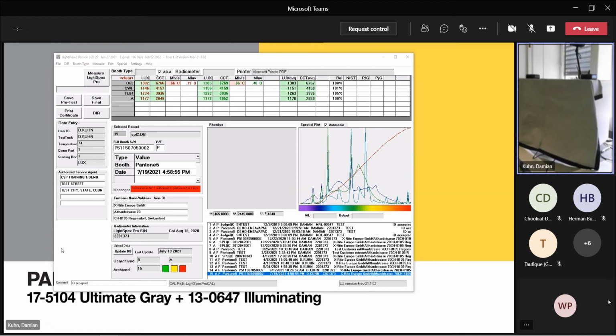So basically, your first step, if you would like to certify this product for a customer, is to connect your Lightspex Pro, position it in the center of the booth, and ensure the first light source is warming up. Then you would start your software, go to booth type, and select the booth you would like to certify. You're going to enter the current ambient temperature. You can leave that on a default value if you want to. We as X-Rite actually have to enter that manually as part of our ISO 17025 accreditation. If you're not accredited, we still recommend capturing it with a thermometer and entering it here, but it's not doing any compensation to the readings you take.